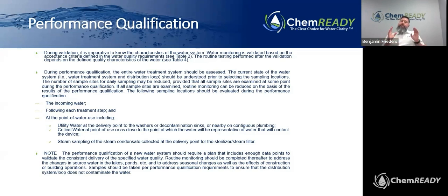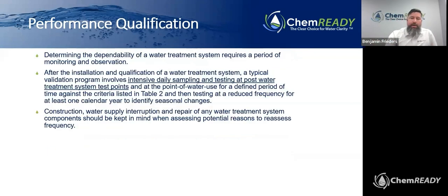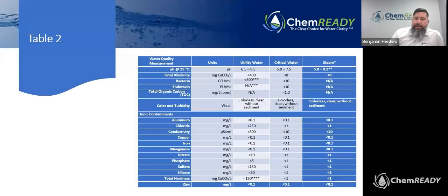Those are required once you get past, and this is a very important note, once you get past the 12 months of the performance qualification, those parameters for critical water are required monthly. And then for utility water, there are parameters that are quarterly. Yes, once you get past the performance qualification, some of the parameters, go back in the slides here. These parameters, pH, alkalinity, there's another table that includes hardness, I believe conductivity is down here. There's a different table. Those are parameters you can do on site as part of your team if you've got the appropriate equipment. The only two you would need to send off to the laboratory would be bacteria and endotoxin, unless you're a hospital and you happen to have that capability, which most hospitals still send those off. But the rest of the parameters can be performed with field measurement tests.